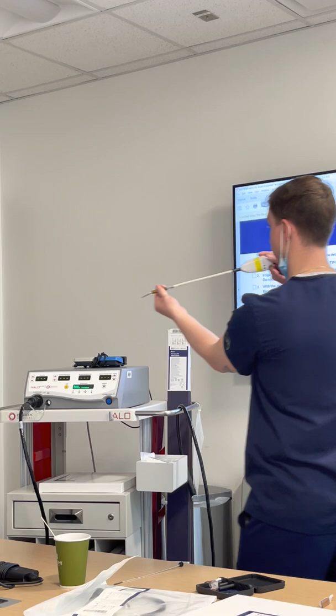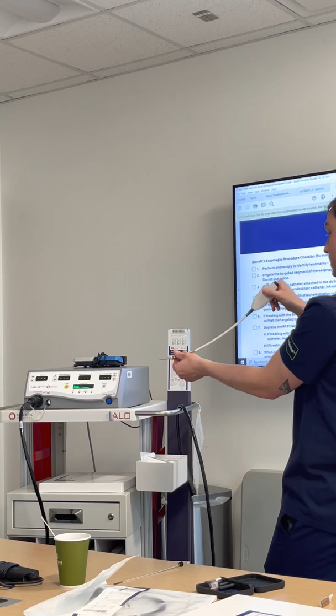If you see the physician or one of you are starting to take this catheter out and we're feeling any resistance whatsoever, please disconnect the catheter from the cord and turn it clockwise. You see, as I'm turning clockwise, that electrode will start to fold back on itself and it will make it easier to pull out. It doesn't happen all the time, but sometimes that just gets extra sticky down there and it'll start to uncoil. If we're finding that resistance, please disconnect the catheter from the system and roll it back on itself. We'll know that it's folding back on itself, even though we're not going to see it because it's in the patient, and we'll start to retract the catheter.